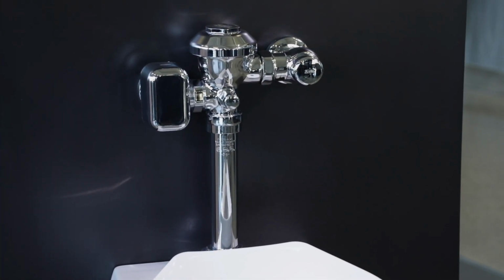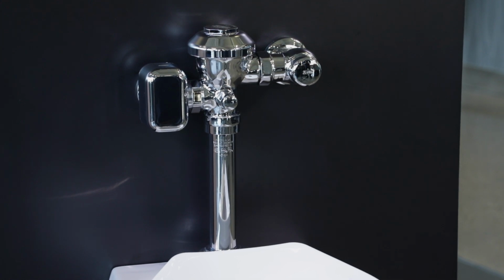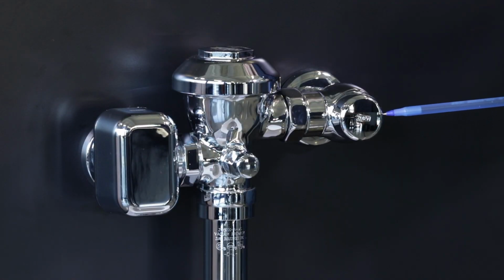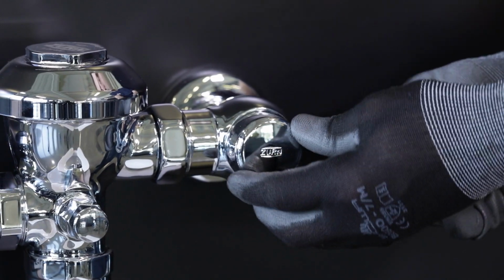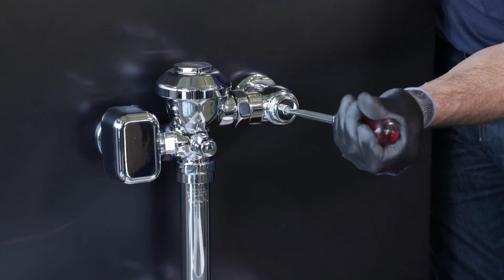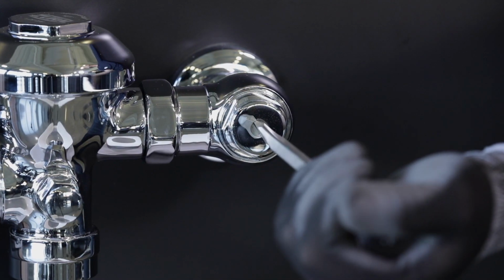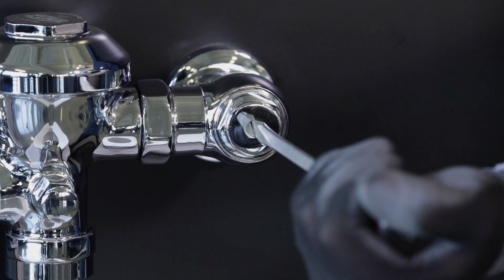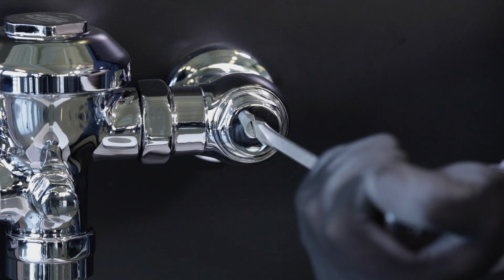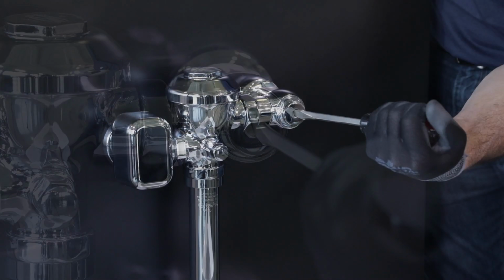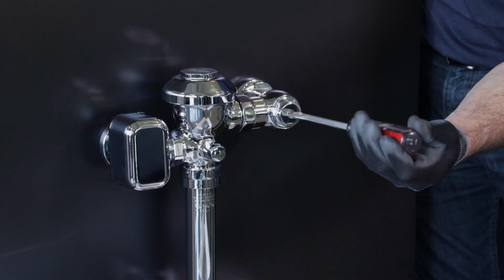Several causes come into play for this problem. Most commonly, the stop valve is completely closed. The stop valve is this component right here. Remove the cap with an Allen wrench. Turn the adjustment screw clockwise with a flat screwdriver to close the valve. Keep turning until you can't anymore. This will ensure no water flows through. You turn the screw counterclockwise to open the valve.